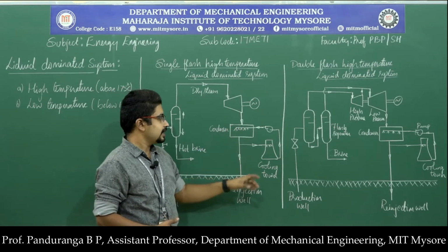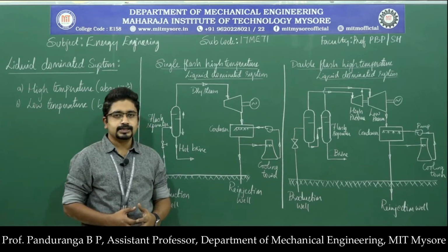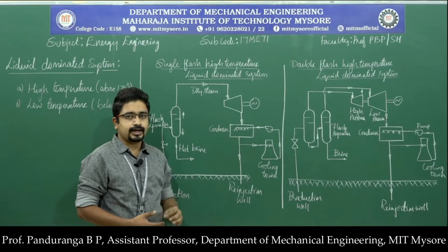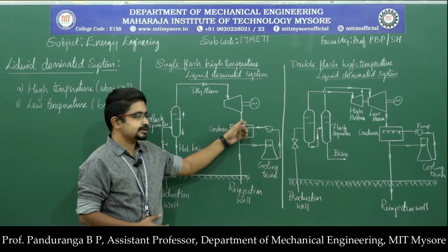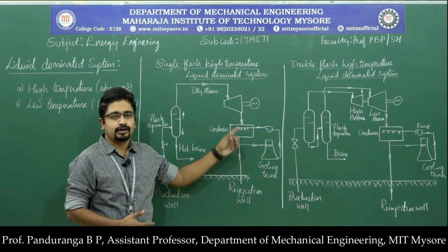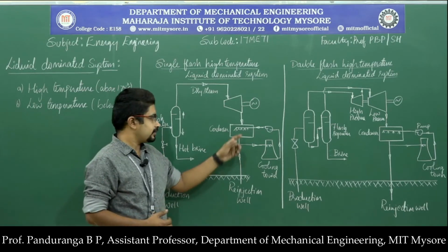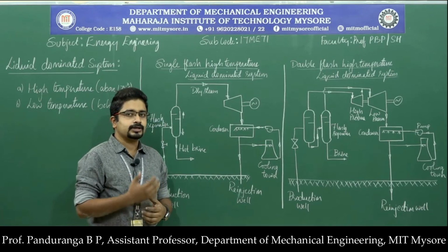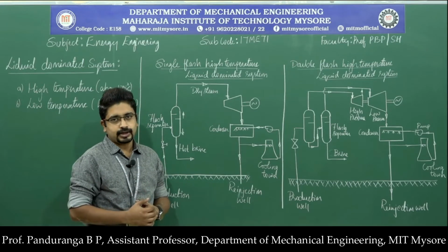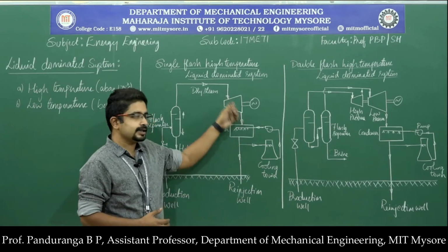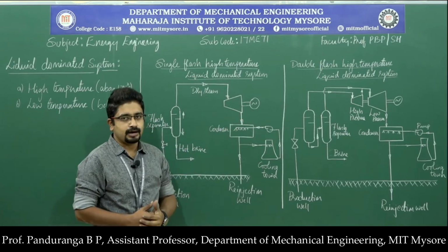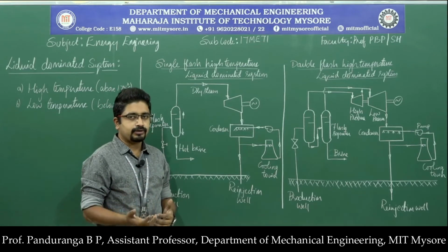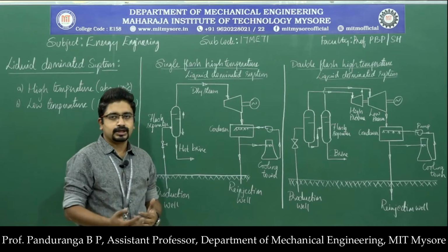So for that purpose, here we have a cooling tower which supplies cooling water for the direct contact condenser. So this is a direct contact condenser, where the cold fluid comes directly in contact with the steam coming out of the turbine. So the water mixes with the steam and absorbs heat energy that converts the steam into liquid water. By doing so, we are also increasing the pressure difference across the turbine, which in turn increases the work output, or energy converted from fluid energy into mechanical energy.